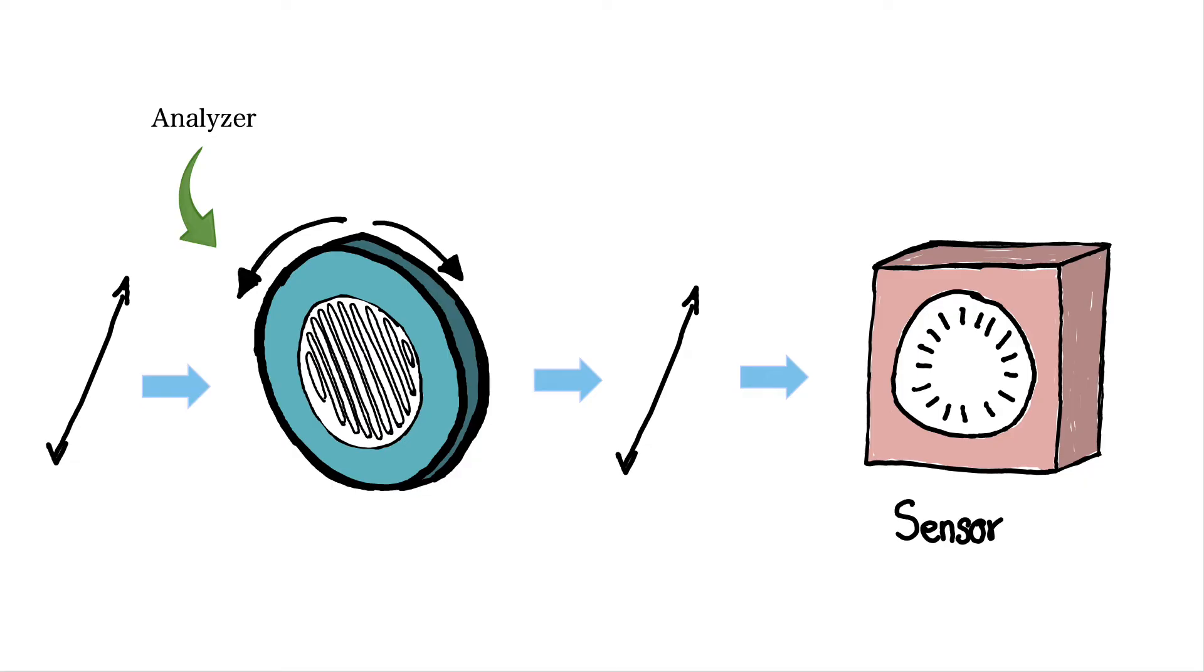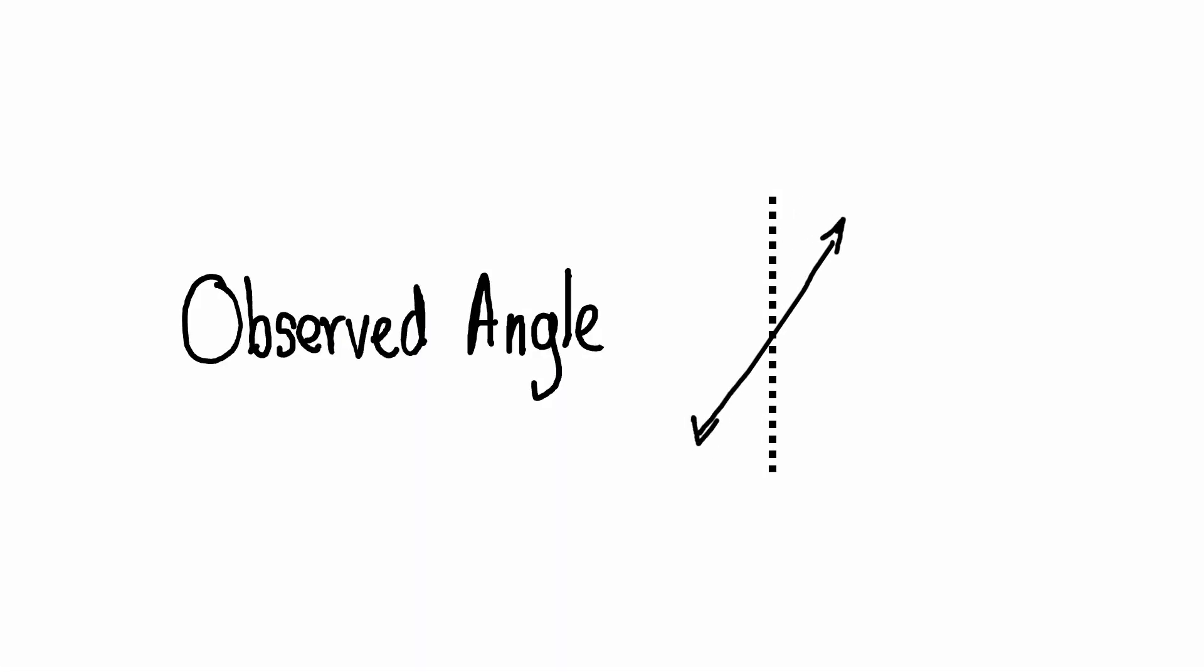Behind the analyzer, there is a light sensor. This sensor detects the intensity of light passing through the analyzer. The angle at which the light passes through completely is then measured. This angle is recorded as the observed rotation of the plane polarized light passing through the chiral sample.